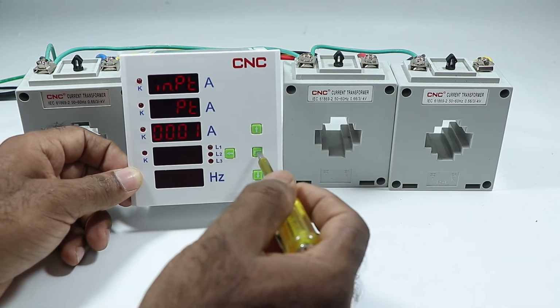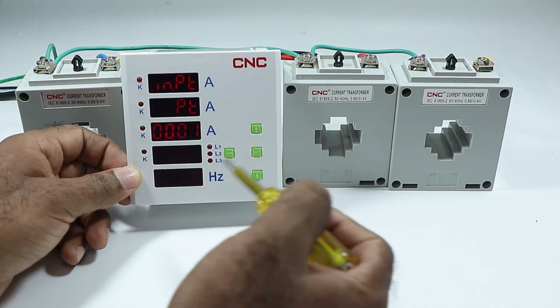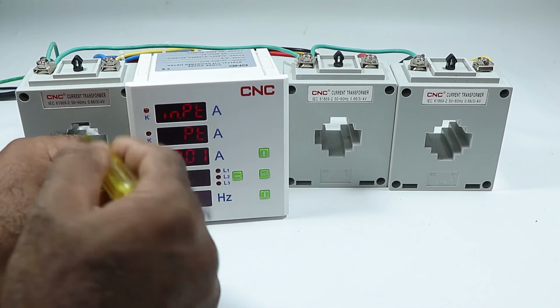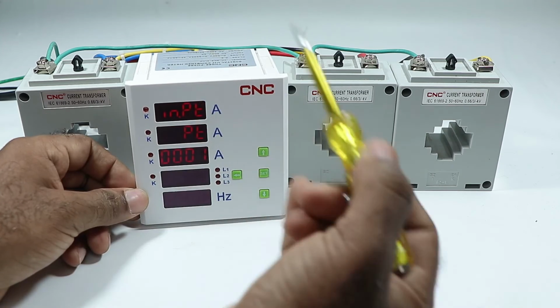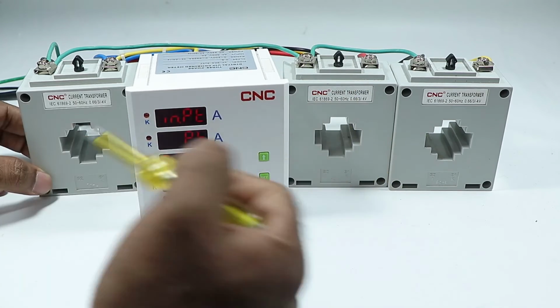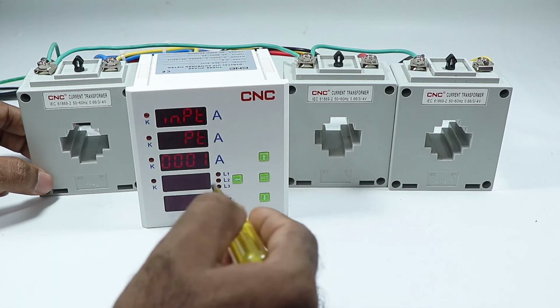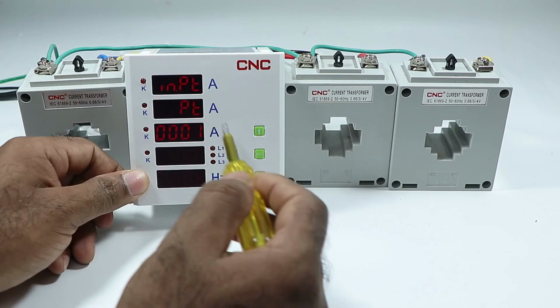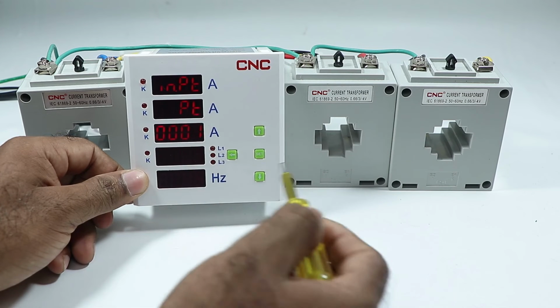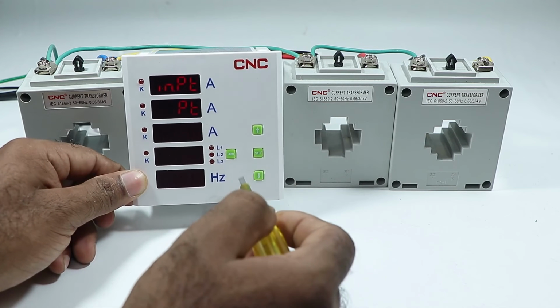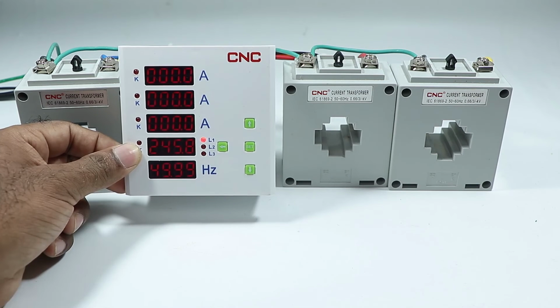For programming, press the set button, and some digits will be displayed. Just like we calculated the multiplying factor of CT, you have to find the multiplying factor of PT. Right now we are not using any PT, so we write 1 here, meaning the multiplying factor will be 1. It's already set, so don't make any changes. Press this button again, and that completes the programming in this meter.